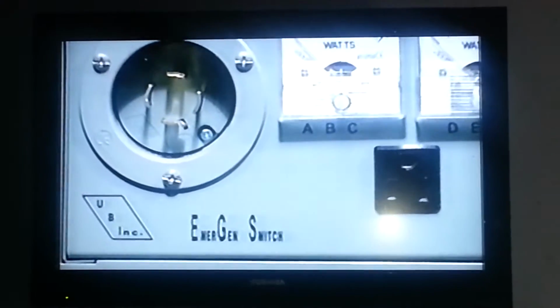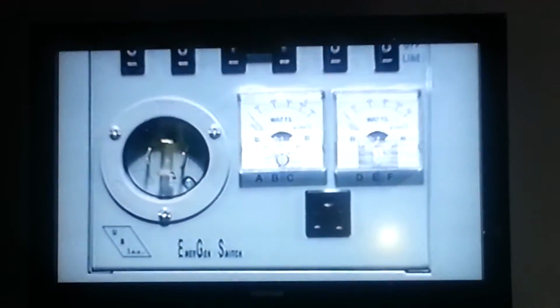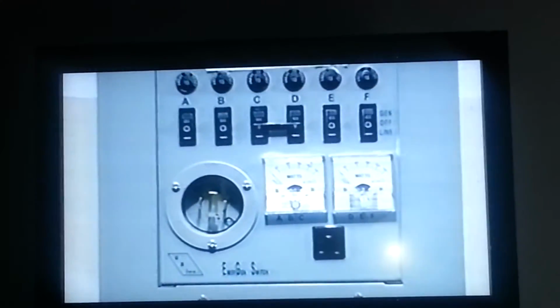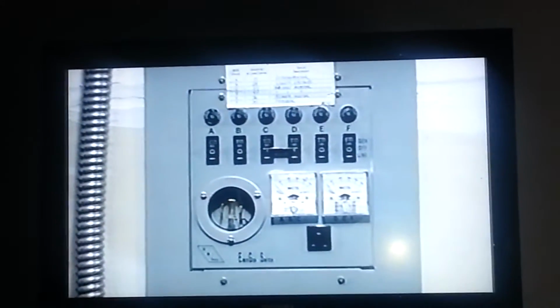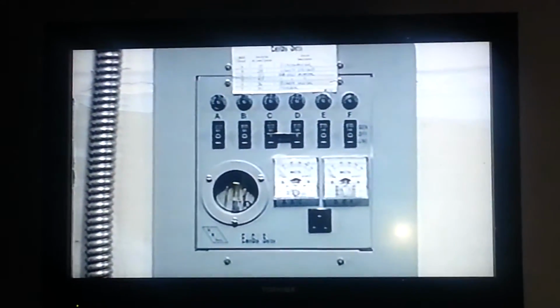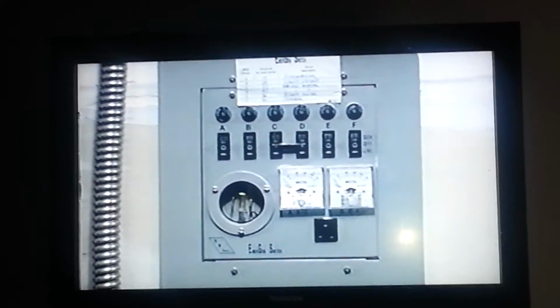For this demonstration, we are wiring to Connecticut Electric's emergen manual transfer switch. Keep in mind that the ATS is compatible with most other brands of manual transfer switch. If your manual transfer switch has a cord whip connection, run the wires from the ATS transfer switch through a knockout in the junction box and connect them to the bare wire ends of your cord whip.